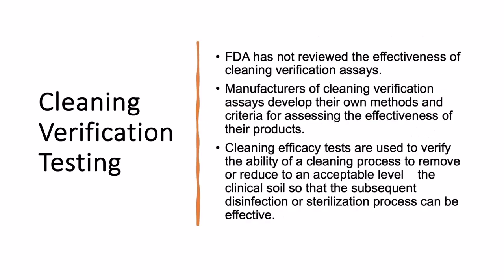Now, understand the FDA has not reviewed the effectiveness of cleaning verification tests. Manufacturers of cleaning verification assays develop their own methods and criteria for assessing the effectiveness of their products. And these tests are used to verify the ability of a cleaning process to remove or reduce to an acceptable level the clinical soil so that the subsequent disinfection or sterilization process can be effective. So it is important to do them. Visual inspection alone is not enough. Cleaning effectiveness tests can measure the level of organic soil on the clean scope more objectively and are a more sensitive test. They quickly verify that adequate cleaning has been performed. Your quality assurance program should include ways to verify that the cleaning equipment is working properly and that the cleaning process is effective. There is an Annex F in ST91 that has a lot of information on cleaning effectiveness tests and quality control programs.